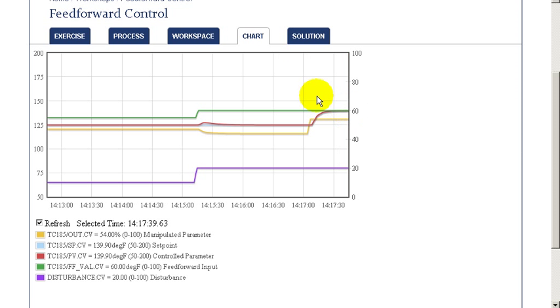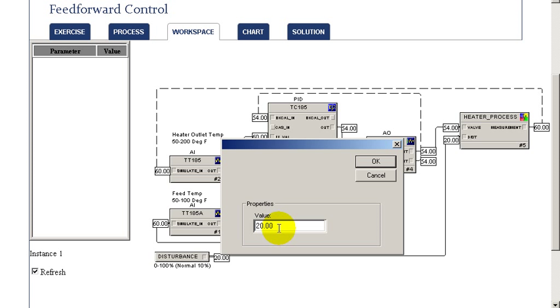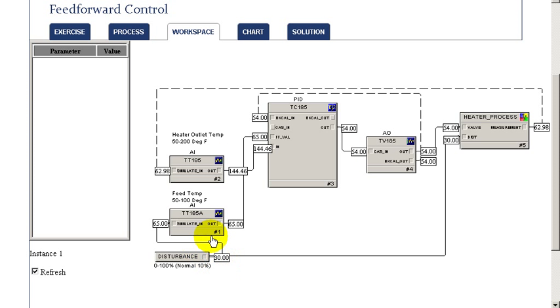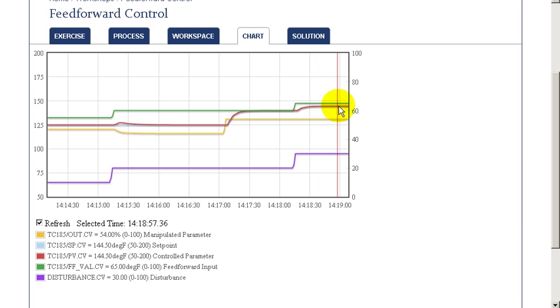Once the temperature has settled, we can then look at the impact of the measured disturbance on our process. We're able to induce a step change into the measured disturbance — about a 10% change. As we can see, it has an impact on the outlet temperature of our heater. With the control in manual, there is no compensation for that, so we can see the true impact of the disturbance with no corrective action. In this case, we can see there is a much smaller impact on the outlet temperature.